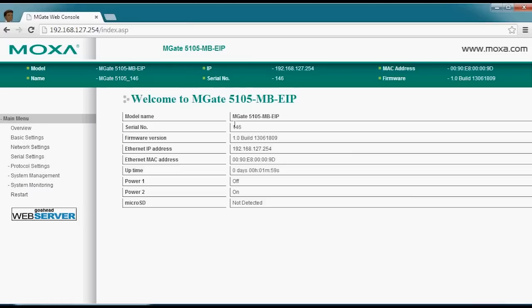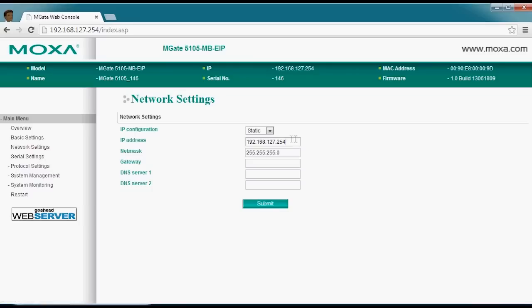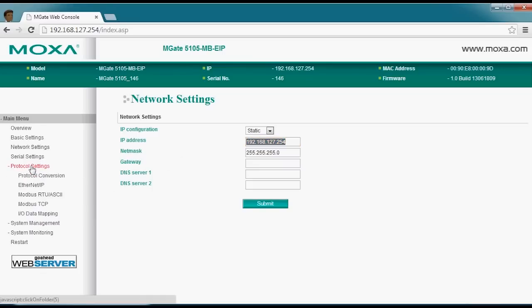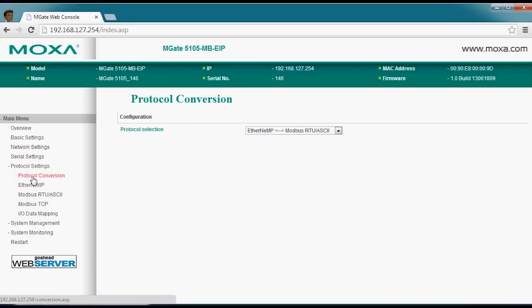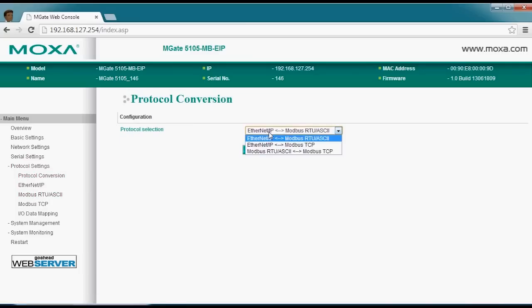There are really three things that you need to set: your network address, your protocol conversion options, and the specific settings for the devices you're working with. The network settings are utilizing the default options out of the box, which makes it easy without much work. Next, going into the protocol settings, you'll see several options when you expand this menu. For the protocol conversion type, we're going to use Ethernet IP to Modbus — let's make that selection and submit those changes.